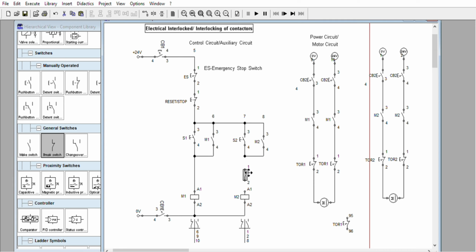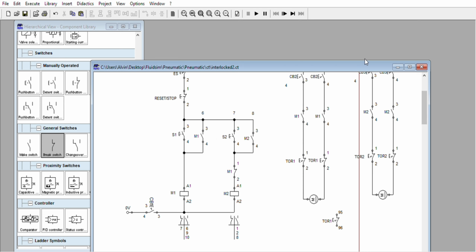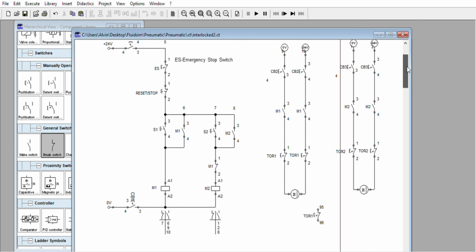You can change this one as CB3. If the motors have different power, you're going to use 2 circuit breakers here. And in reality, this auxiliary contact is connected here. You have the auxiliary transformer. This should be the main CB, either of this one. You have the third circuit breaker as per electrical code. One main CB here connected as your local electrical code requirements.